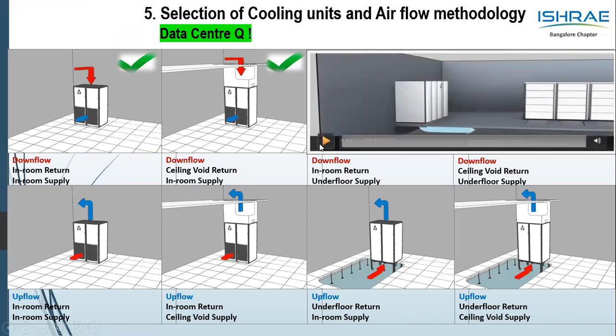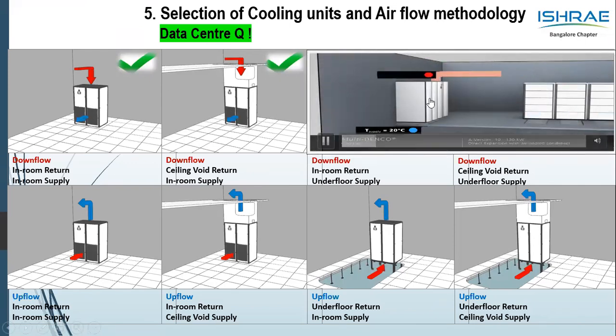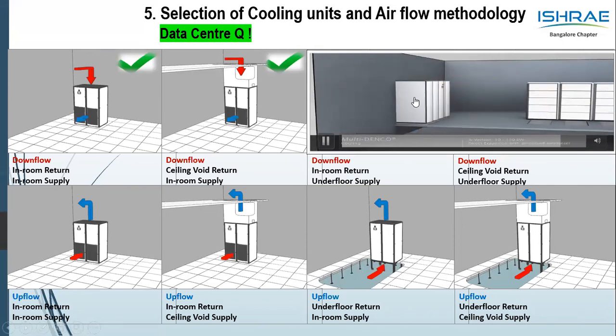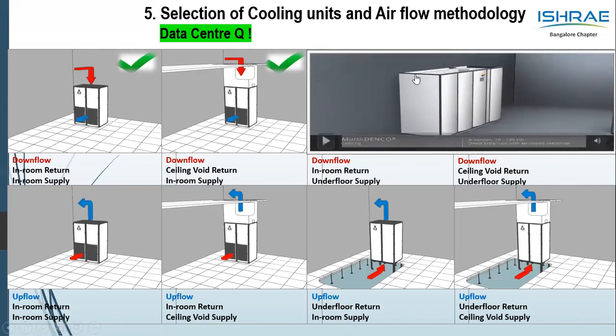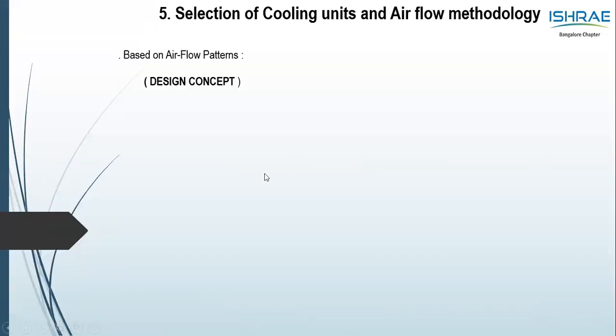the CCU. Here you could see a quick video. This is the CCU. The cold air goes here and picks up the heat, and the red is the hot air, which goes back naturally to the unit. If you have a false ceiling, yes, you could have. And then if you have multiple units, it's recommended to have a plenum and a damper. We don't want the hot air going back to the standby unit. So, a couple of videos and the design concept on the airflow.